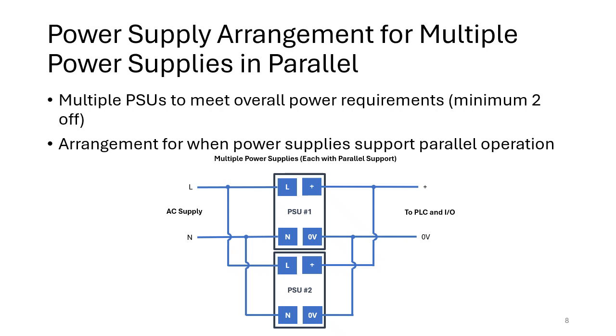Now, it might not be necessary to use a redundancy module. The reason for using the redundancy module is it allows us to have a power supply arrangement where you've got two power supplies operating in parallel. So you need minimum 2, and this would be ideal for power supplies which do support parallel operation. So typically what we have here is we have the two AC supplies coming in, that's split out to the two power supplies, and then they are just combined together on the output side and go directly to the PLC and the I/O. You need to make sure that your power supply is designed for parallel support though.